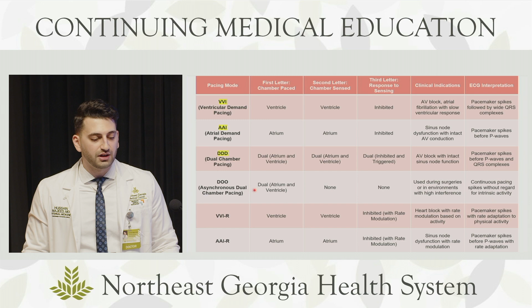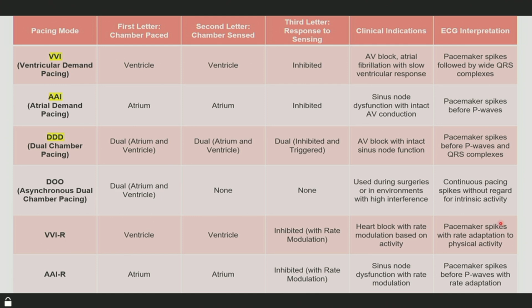We've also got DOO, so both chambers are being paced, but there's nothing being sensed and there's no response to the sensing. You can see that in patients where this can actually be changed from VVI to DOO, for example. Let's say that they're in surgery and the anesthesiologist wants complete control of the pacing, so they can set a certain rate to the ventricle and ignore whatever the atrial paced rhythm is and take complete control of that.